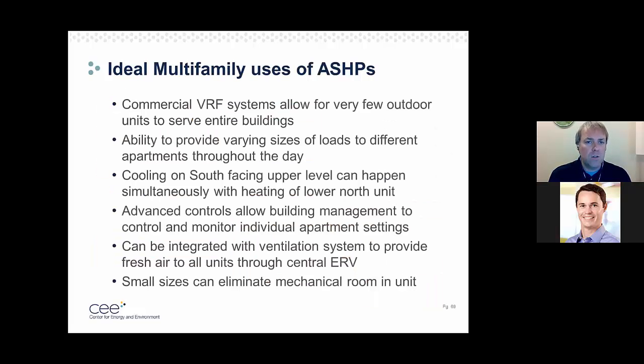So the ideal uses of the air source heat pumps: commercial VRF systems allow for very few outdoor units to serve the entire building. They're a good solution for a bigger building when you want to go for an air source heat pump, with the ability to provide varying size of loads to different apartments throughout the day.